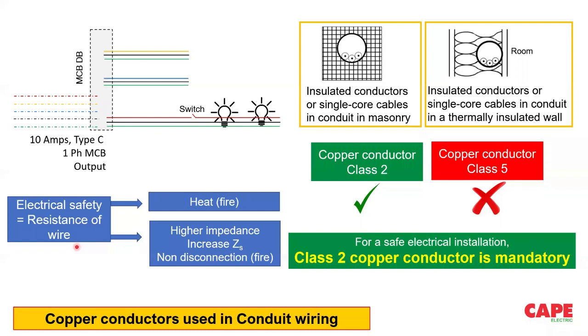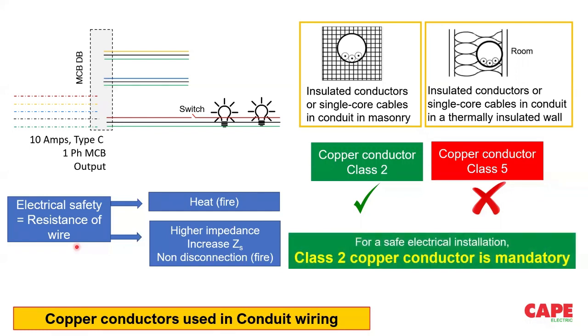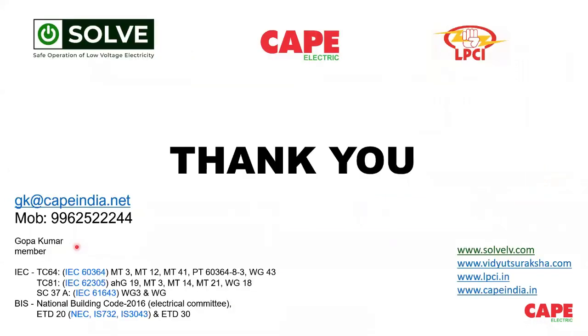Unfortunately, both class 2 copper wire and a type B MCB are not available in the market. I repeat, for a safe installation, class 2 wire, I am talking about the smallest wire which is used in our house, class 2 copper wire, and type B MCB are not readily available in the market. So this is the actual fact of the installation.